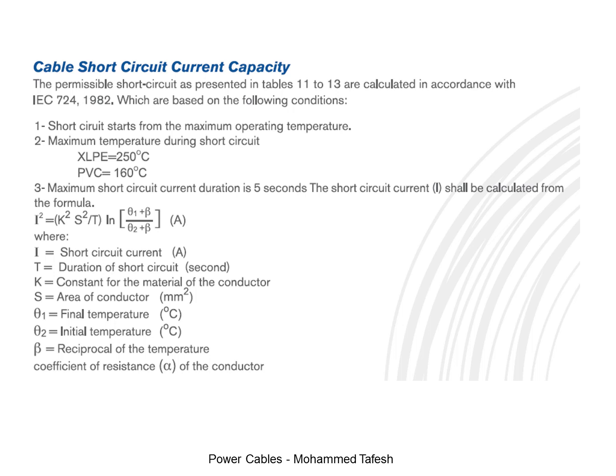My friends, I'm going to discuss and display for you the equations of cable short circuit current capacity. The permissible short circuit, as presented in tables 11 to 13, are calculated in accordance with IEC 724-1982, which are based on the following conditions.